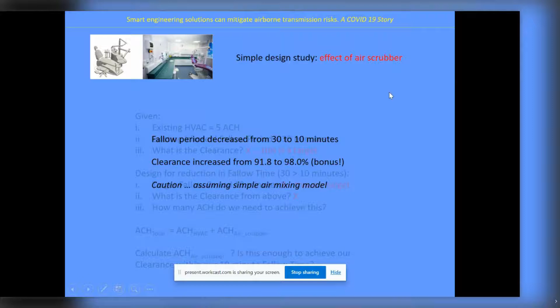Caution, this assumed a simple air mixing model. In this particular scenario, where they were getting a clearance of 92% using the hospital's HVAC system, adding an air scrubber that's available, it happened to be the Mansfield Pollard device I've already shown you, they could get away with a 10-minute fallow time as opposed to 30. And the bonus, the clearance went from 92% to 98%.